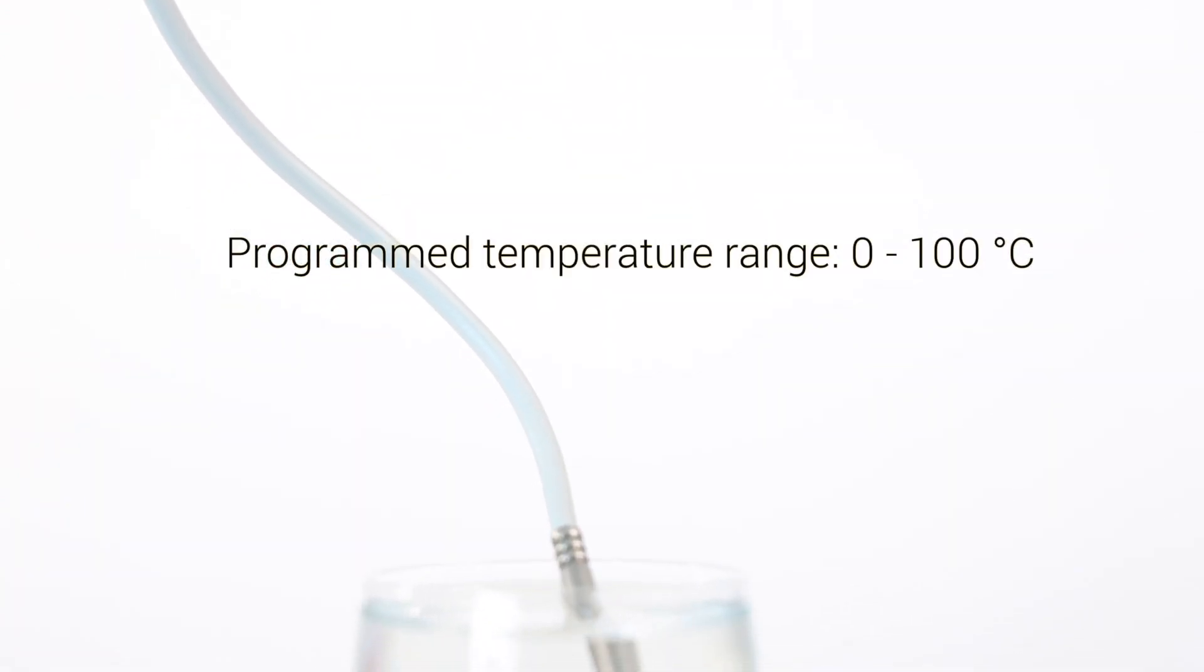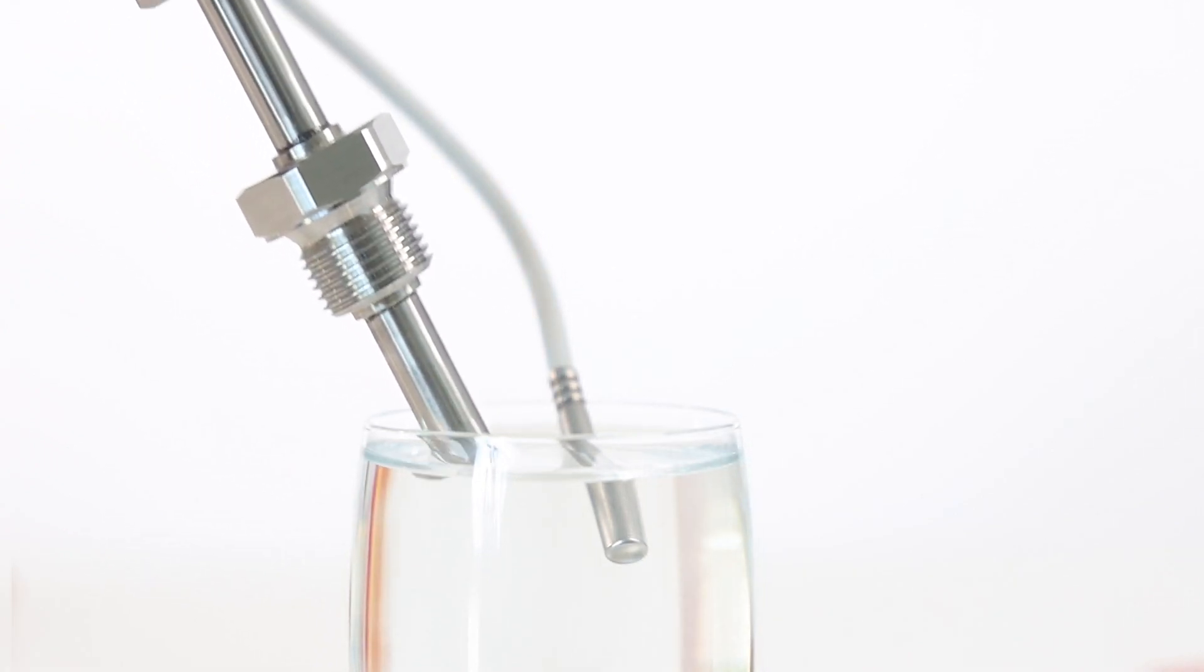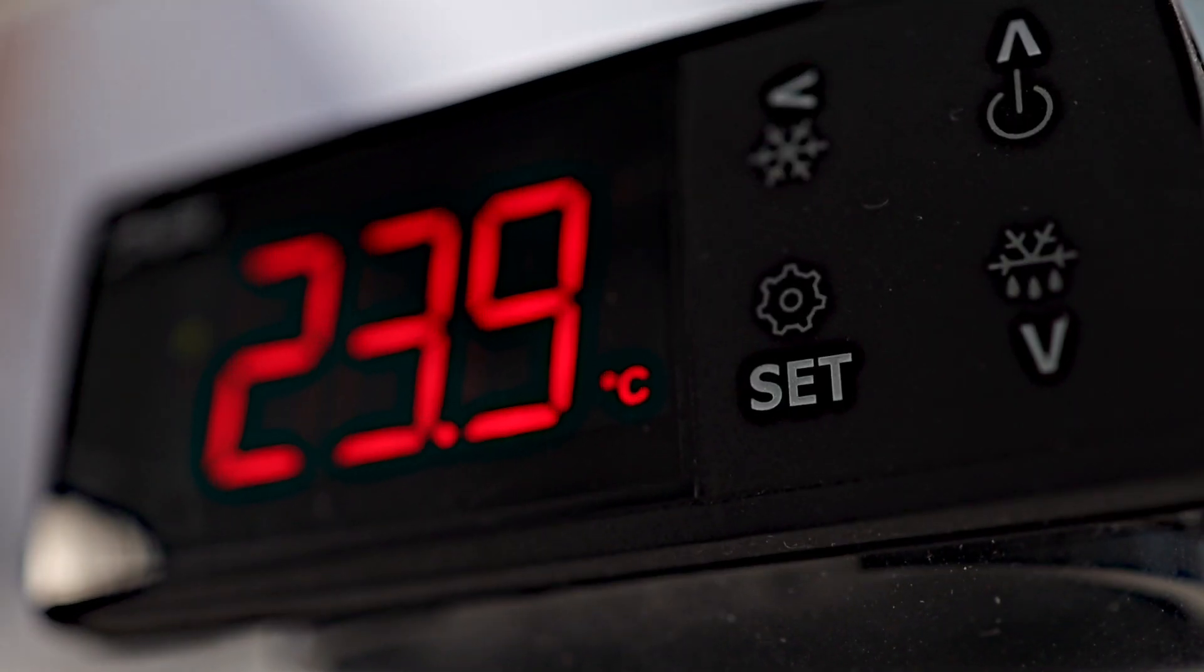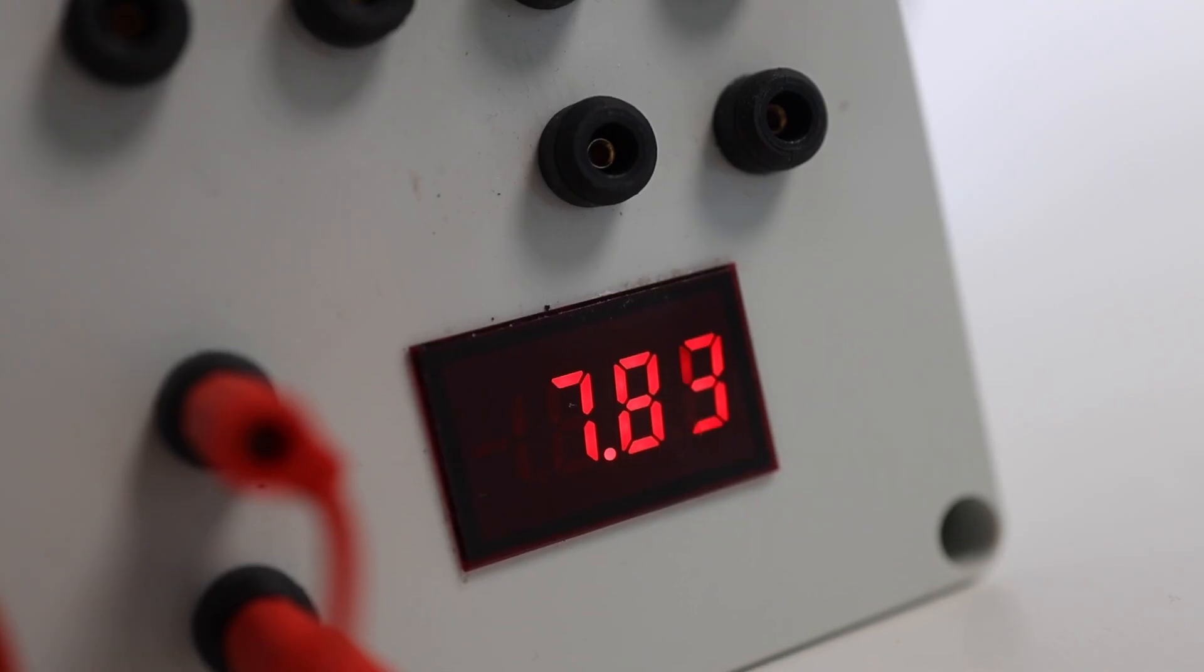The transmitter in our example is programmed from 0 to 100 degrees Celsius. Let's look at this example where the transmitter is inserted into water that is 24 degrees Celsius. The thermometer shows 24 degrees Celsius and the sensor output on the milliamp display shows 7.83 milliamp.